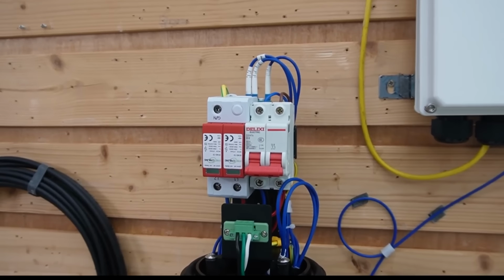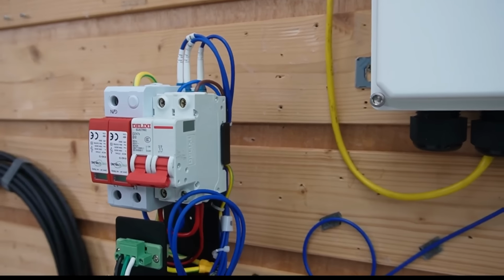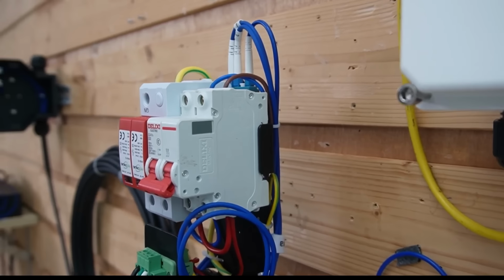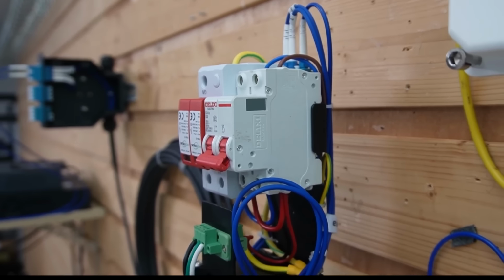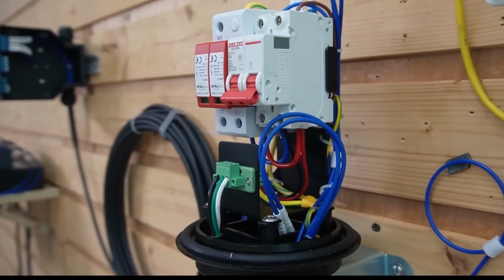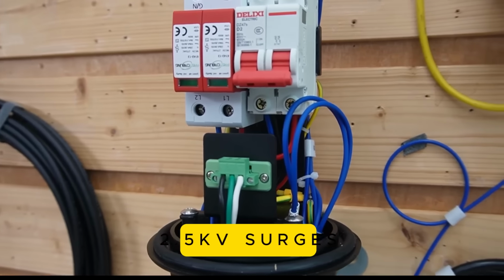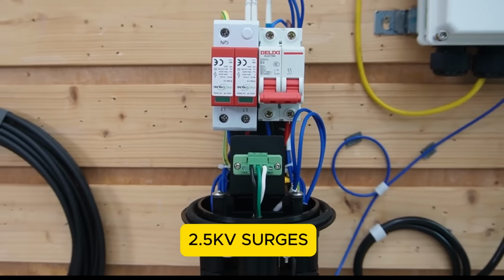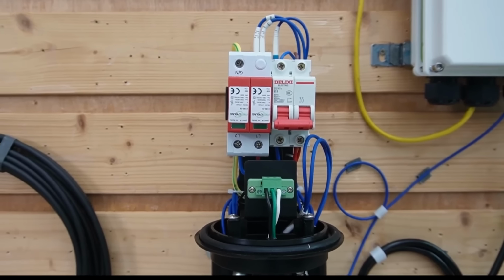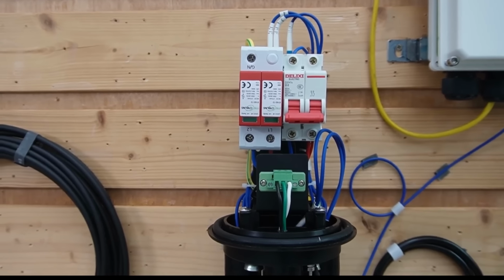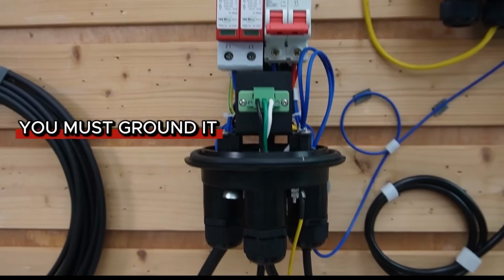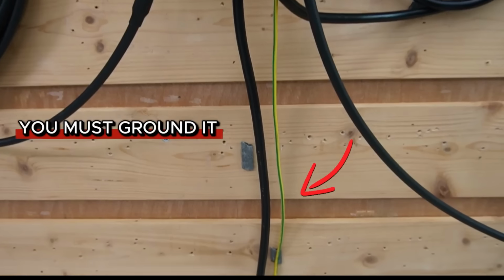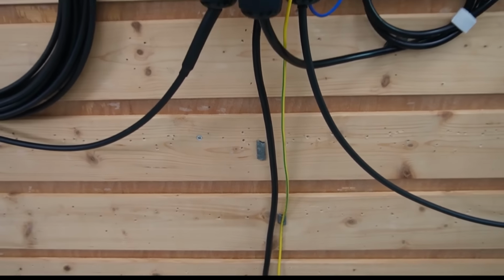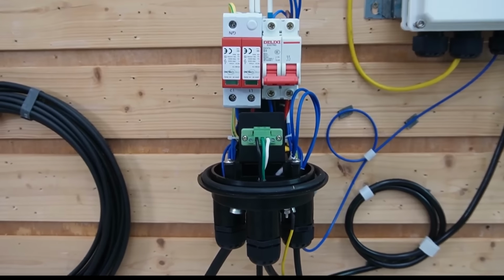If a power surge from a lightning strike or grid instability comes down the line, this protector absorbs that massive jolt. It's rated for 2.5 kV surges and responds in less than 25 nanoseconds to clamp it down. But you must ground it, this is very important. It also has a built-in fuse to stop excessive currents.